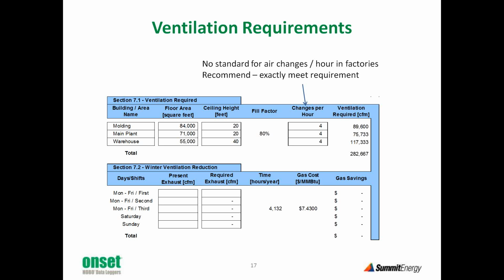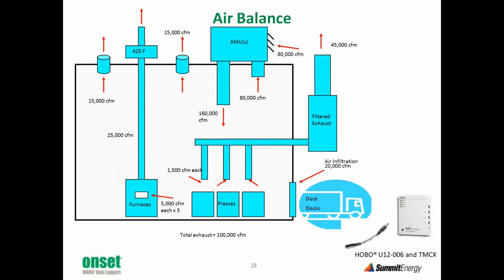If you have no idea what your ventilating system is doing, get a quick calculation as to how many changes per hour you have. Now, there's no standard for the number of changes. The recommendation is, if it's a factory or an area where there's no concern about CO2 levels, then the best approach is to simply minimize the ventilation. You may have smoke or mist or other things that have to be taken out of the environment that will drive the ventilation requirement. In a space where it's dominated by people, if this is an office or a restaurant or a school, then you need to measure CO2 levels and implement demand ventilation, where you have controls that only bring in the amount of air that's required in order to maintain the CO2 levels.